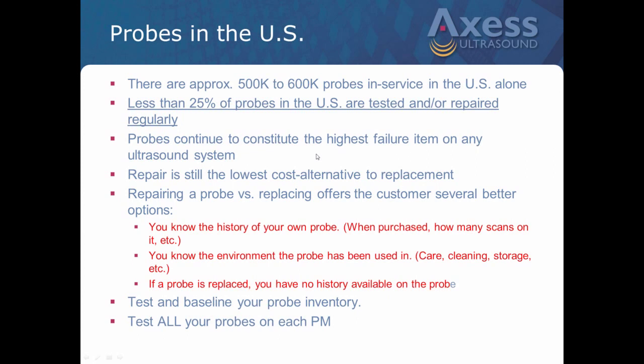Just a little bit about probes in the U.S. alone. By estimation, there's upwards of 600,000 probes in service in the U.S. alone. On average, what we find historically is that less than 25% of those are tested and or repaired regularly. And I mean tested in a very proper way. The probe continues to constitute the highest failure item on any ultrasound system. And those of you doing ultrasound service and support, I'm sure you know that.